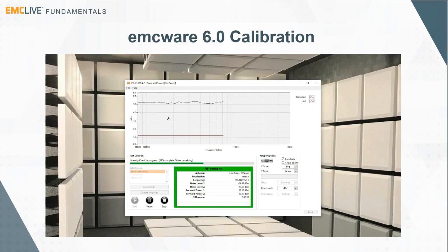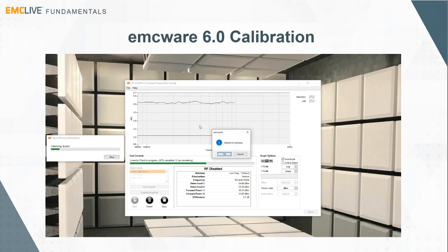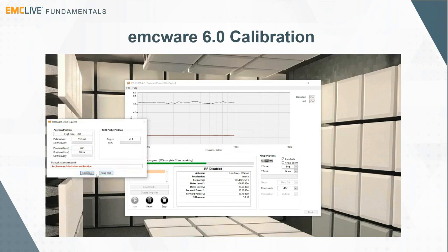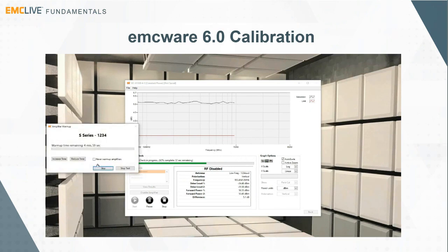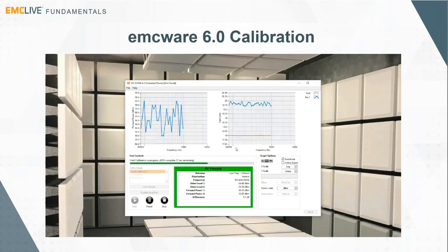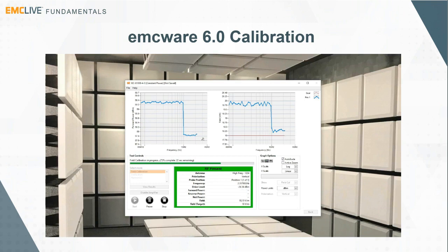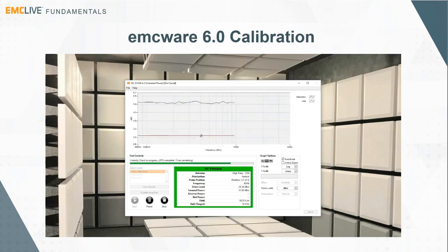This is a good way to give you an idea of how much overhead you have when you're doing two-tone tests. And here's our breakpoint at 6 gigahertz. Switching antennas. Skipping through that quickly, and it'll run through very quickly. Again, a shortened profile for demonstration purposes. I have this set to 10% step size and a shortened frequency range.